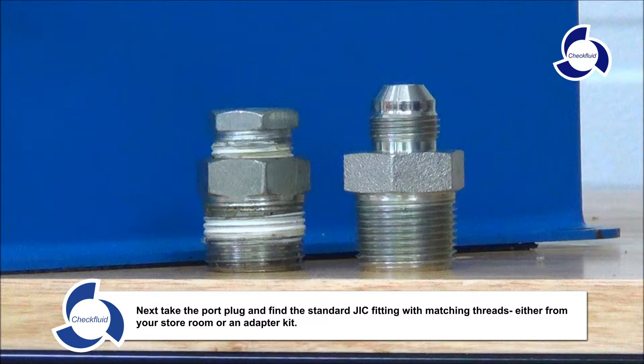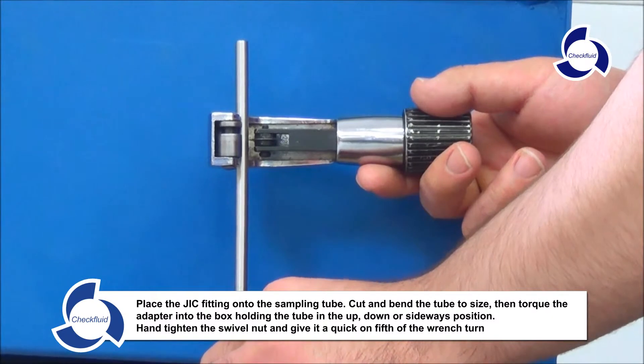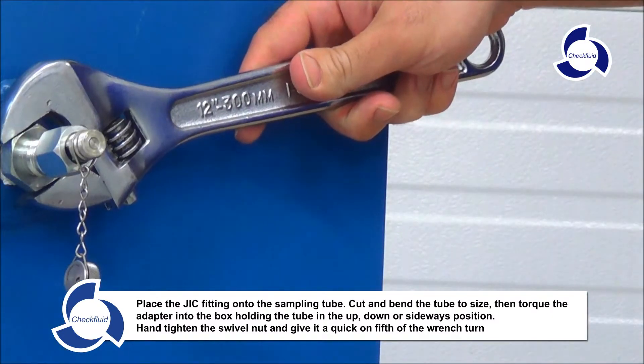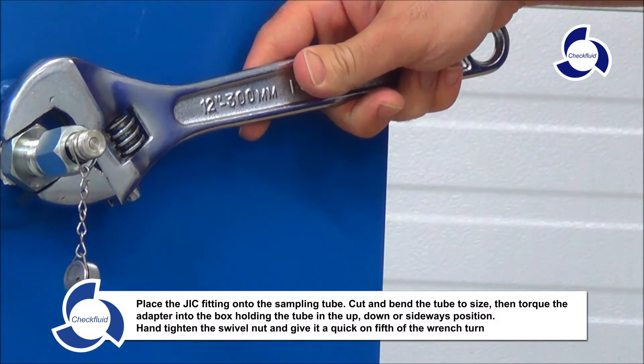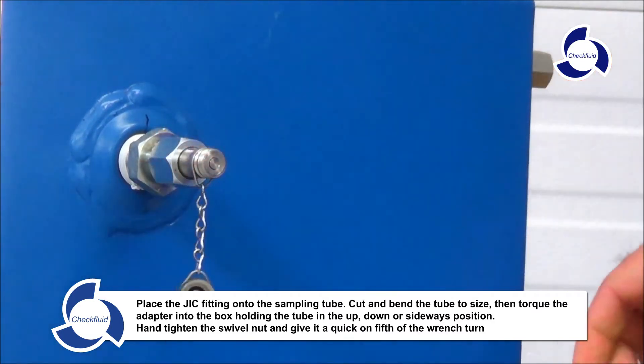Checkfluid also has adapters available. Place the JIC fitting onto the sampling tube. Cut and bend the tube to size. Then torque the adapter into the box, holding the tube in the up, down, or sideways position. Hand tighten the swivel nut and give it a quick one-fifth of a wrench turn.